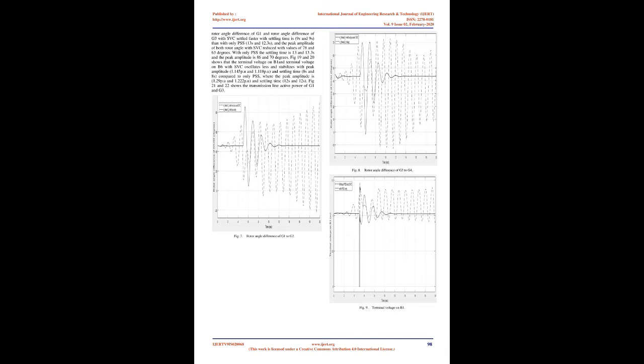to simulate a signal proportional to the integral of change in mechanical power by adding signals proportional to shaft speed change and the integral of electrical power change. On horizontal shaft units, this signal will contain torsional oscillations unless a filter is used. Because mechanical power changes are relatively slow, the derived integral of mechanical power signal can be conditioned with a low-pass filter to attenuate torsional frequencies. The overall transfer function for deriving the integral of accelerating power signal from measurement of electrical power and shaft speed is given below. Equation 4, where G(s) is the low-pass filter's transfer function.